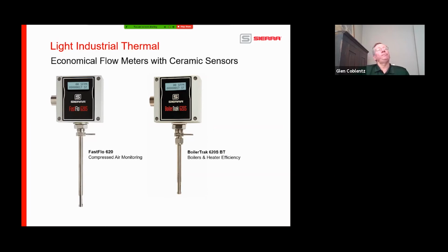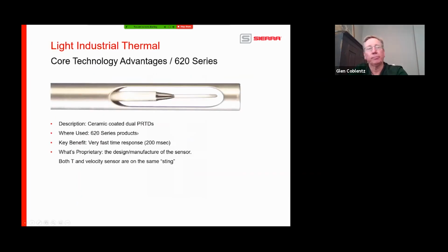Light industrial thermal. These are economical flow meters, and they have ceramic sensors. So these do not have the lifetime sensor warranty. These will eventually drift over time and will have to come back. Okay, it's the same exact product, except this one can be powered by 24 VDC. This one needs to be powered by 15 to 18 VDC, because you're dealing with explosive gases here.